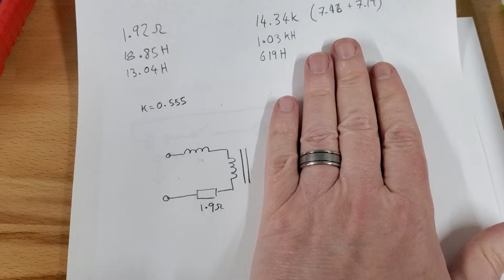The center of the secondary winding is actually grounded. So the case is ground. There's a ground screw here. So there's only 3,750 volts each side to ground, and it reduces the insulation requirement and the shock hazard of the transformer. Almost all neon sign transformers are built that way. Obviously, modern ones are completely different. They're a switching ballast, and they'll be much smaller because of the higher frequencies.